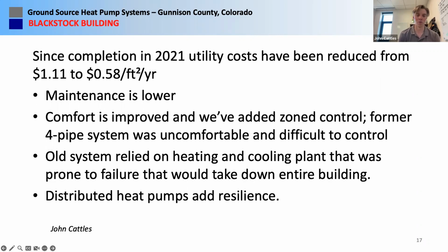The former strategy was a distributed system of fan coils. So to simplify the process, we developed our building loop, our water loop throughout the building, and then we would remove one fan coil at a time and replace it with a heat pump plugged into the geothermal building loop.